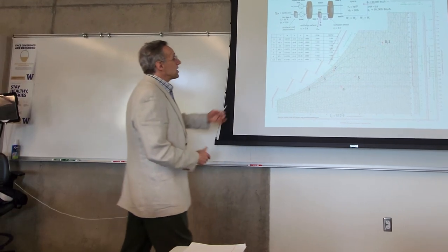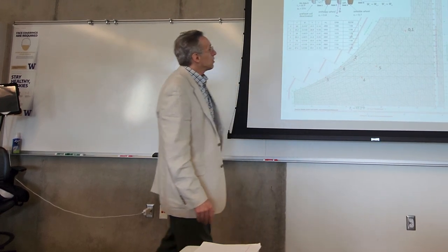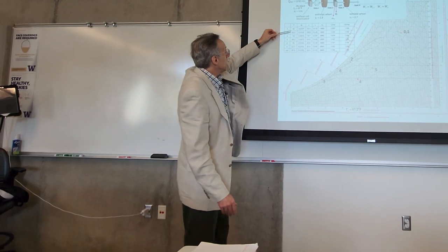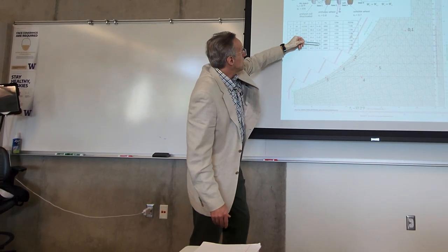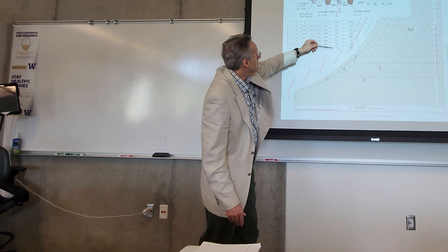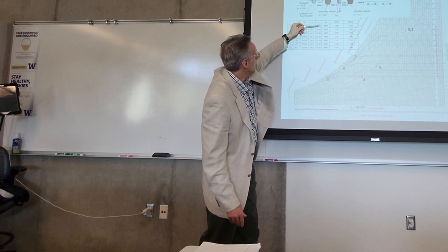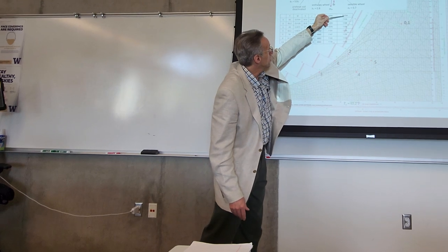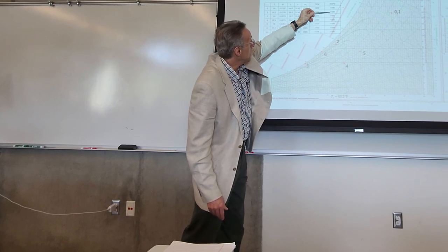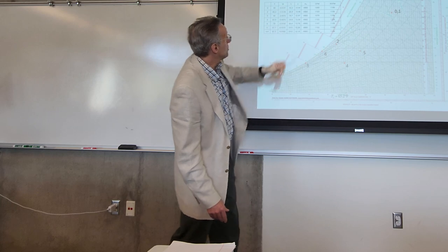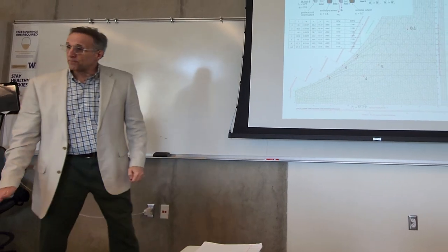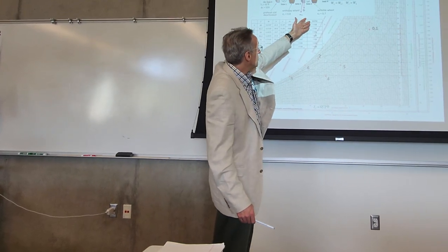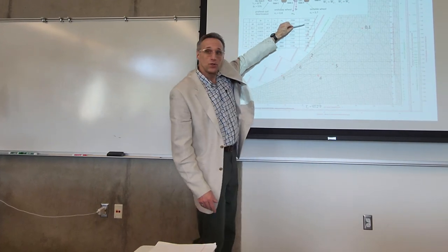But anyway, so we take all of the properties and we put them here on a table. That's what they look like. And then I just calculated the CFM based off of the mass flow rate and the specific volume at each point, and then adjusted them to the standard. This should be the same all the way through, since it's just one stream of air. We're not combining streams of air. So 1109 SCFM. So that's what we would size our fan to.